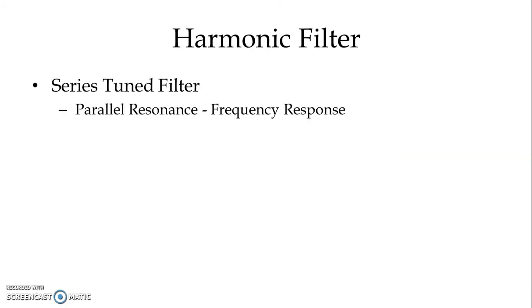We have to consider parallel resonance and check the frequency response, because harmonics will be filtered out but at the same time the impedance of the series tuned filter will generate a parallel resonance with the source impedance, which can have a very adverse effect.